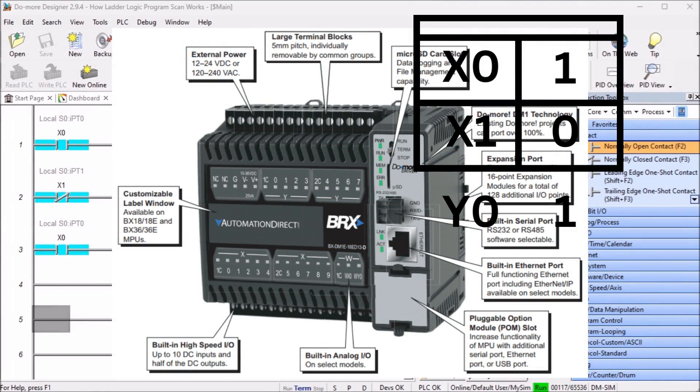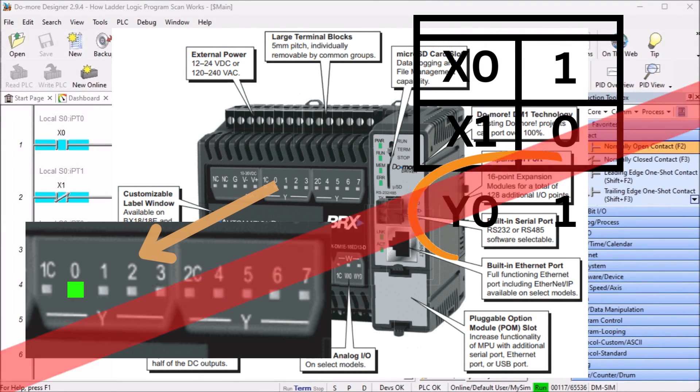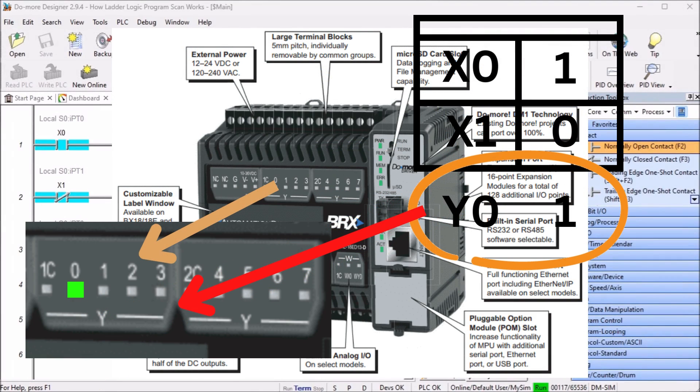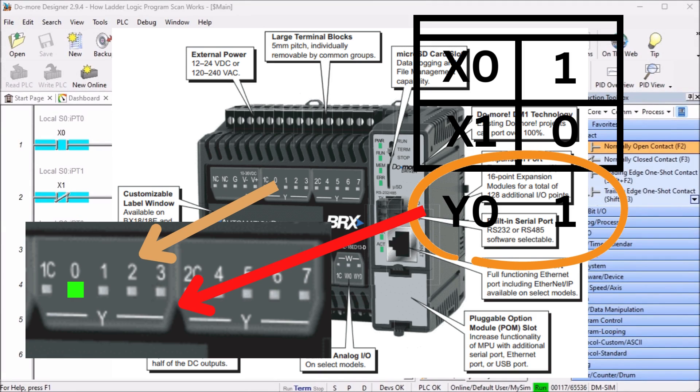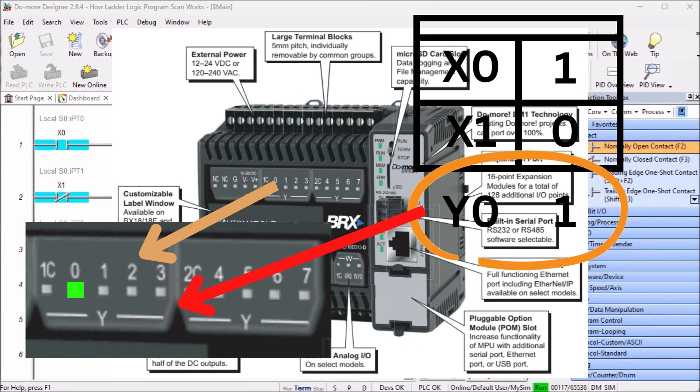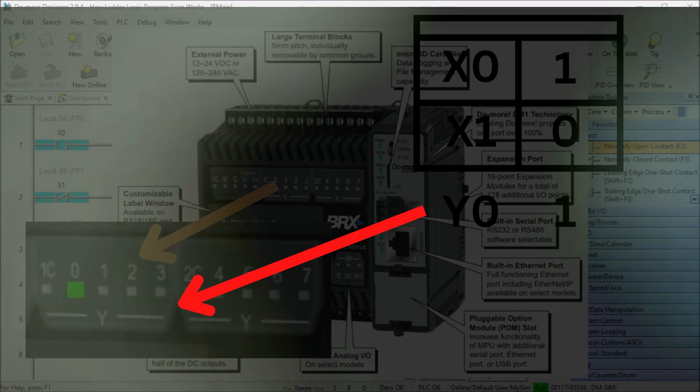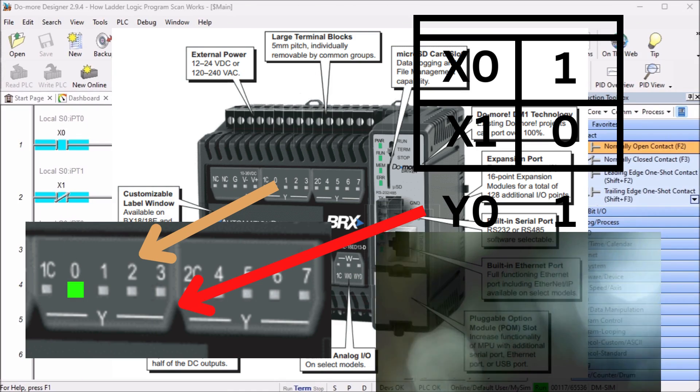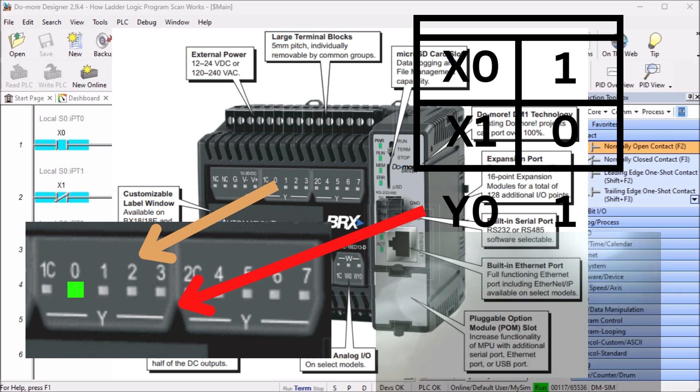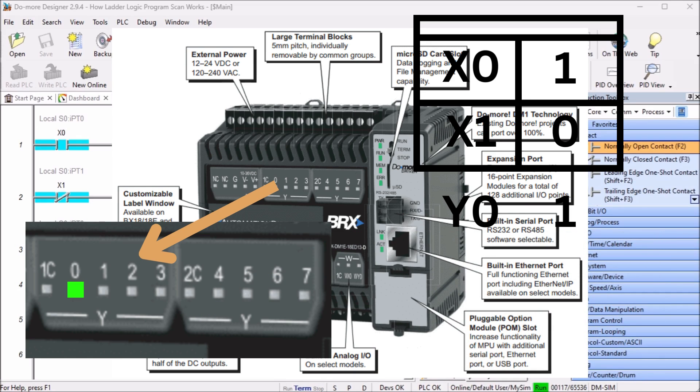PLC physical outputs are updated once per scan. The memory table for the outputs is copied to the physical outputs. This will activate your lights, relays, etc. The outputs are optically isolated from the PLC CPU unit, just like the inputs. The CPU will be protected by the optical isolation. If the outputs are destroyed by faulty wiring or surges, usually it is only the output or card that is needed to be replaced.